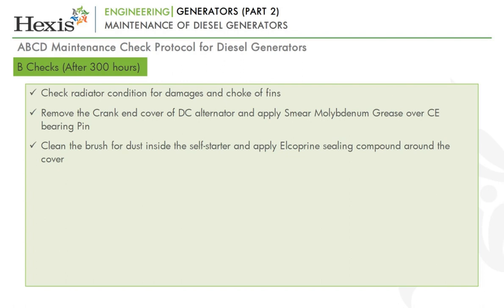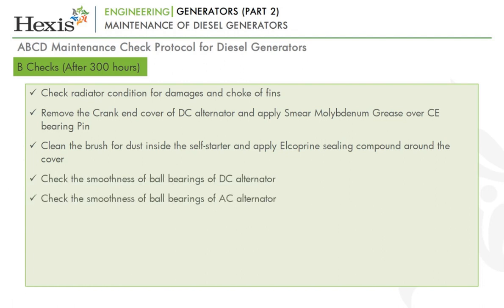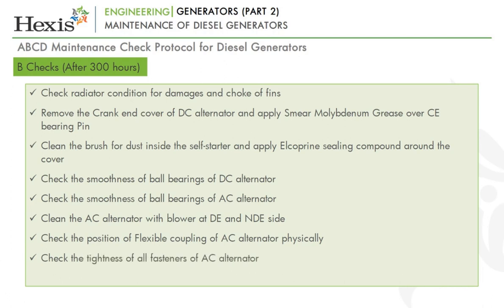the cover. Check the smoothness of ball bearings of DC alternator. Check the smoothness of ball bearings of AC alternator. Clean the AC alternator with blower at DE and NDE side. Check the position of flexible coupling of AC alternator physically. Check the tightness of all fasteners of AC alternator.